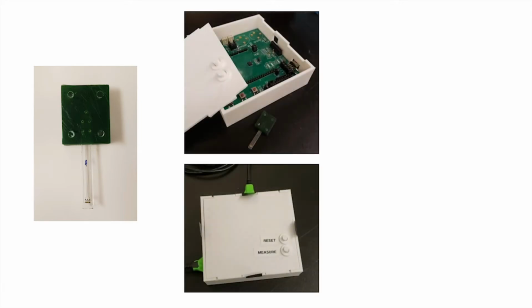So here you can see there's a chip that's on a glass substrate, again with gold working, counter and reference electrodes, and with a clamp for the interconnects. Another thing we're doing is we're using ADI's ADuCM355 SoC as our potentiostat. We've configured the ADuCM355 to take high-resolution measurements on a single channel, as is necessary for our tests. When we do our chronoamperometry testing, we need to be able to sample data points every 15 to 20 microseconds. We've developed our system using the evaluation board of this SoC.